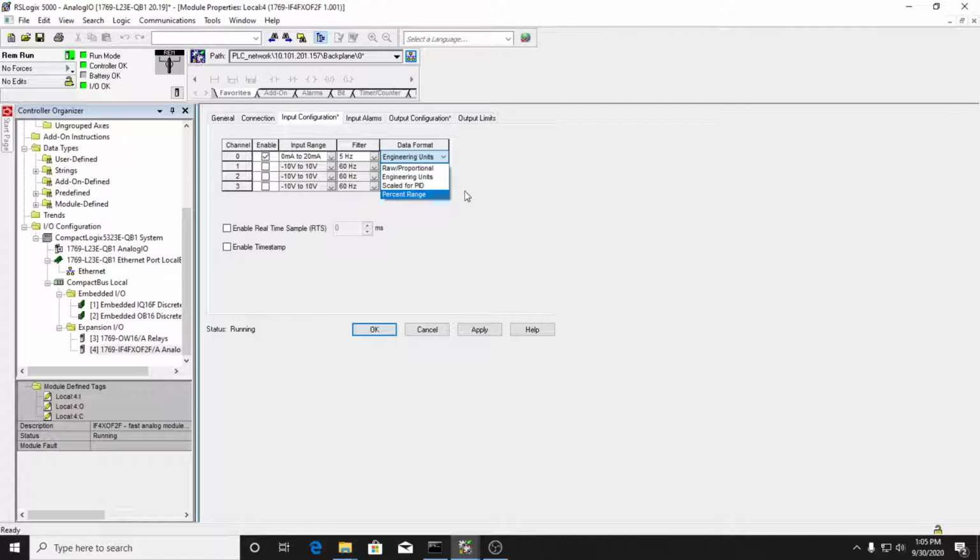If we choose percentage, then we can go from 0 to 100%, but again, it's an integer value. So if you wanted, say, 30.7%, you couldn't do that because it's an integer. So what they do is they scale it by 1,000. So it actually goes from 0 up to like 100,000 for 100%. Or maybe it's 10,000, I forget. But they scale it.